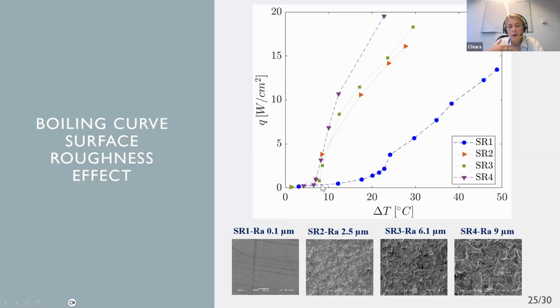This means our electronics can operate at lower temperature if we use two-phase flow. Also, the critical heat flux limit, the last point of these curves, increases to around 18 watts per centimeter squared, compared to 12 for the smooth surface. So we already have a huge increase just from surface roughness modification.